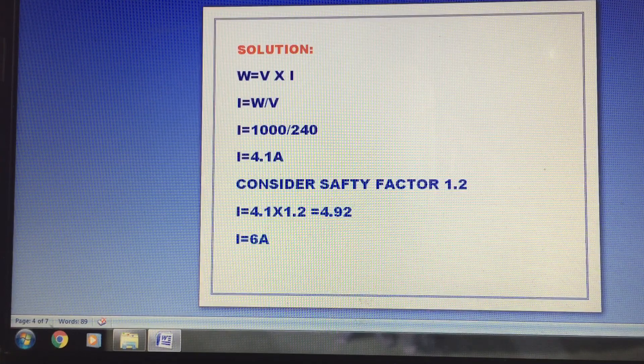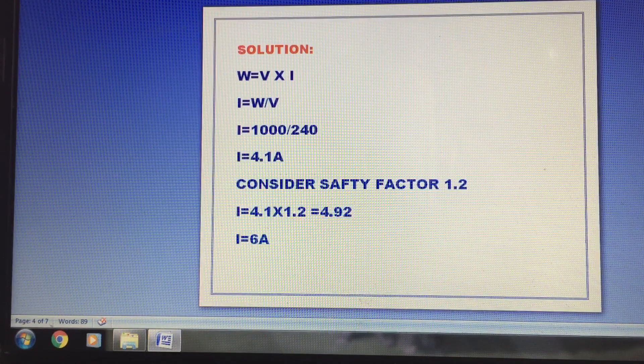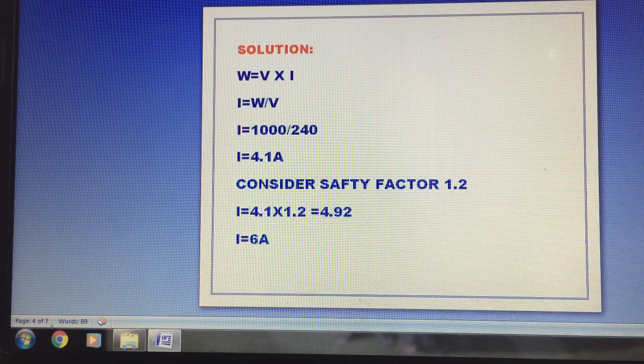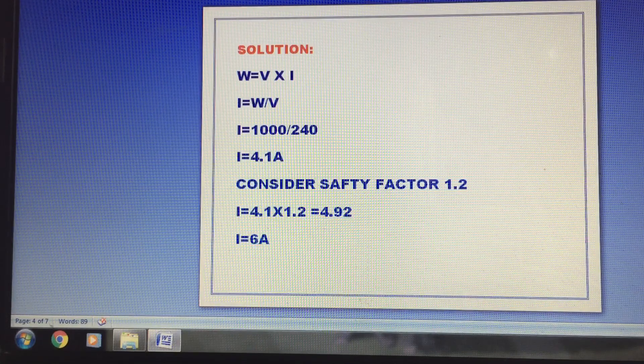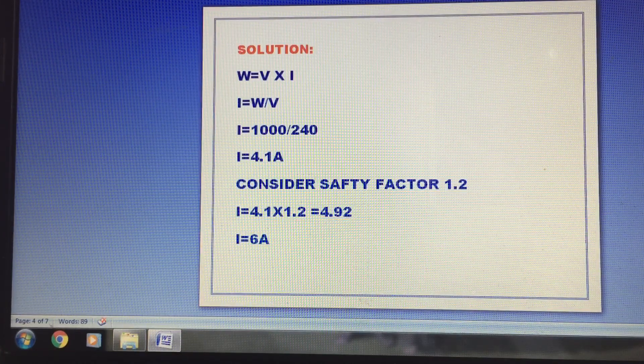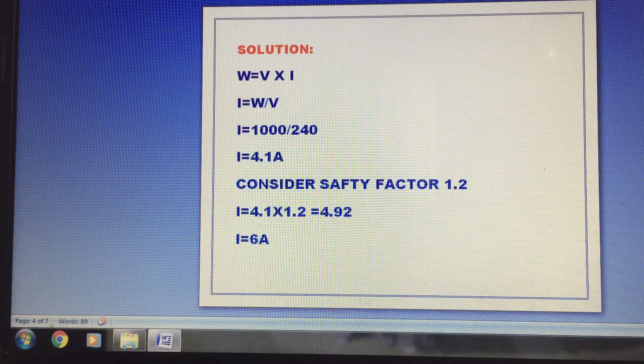So I is equal to W divided by V. I is equal to 1000 divided by 240 volt. So I is equal to 4.1 amps. This is the required current. We apply a safety factor of 1.2, so I is equal to 4.1 times 1.2, giving I equal to 4.92 amps. From the market, the available breaker is 6 amps. So the MCB design is complete — it is simple.